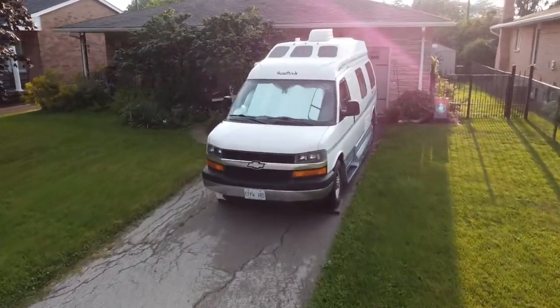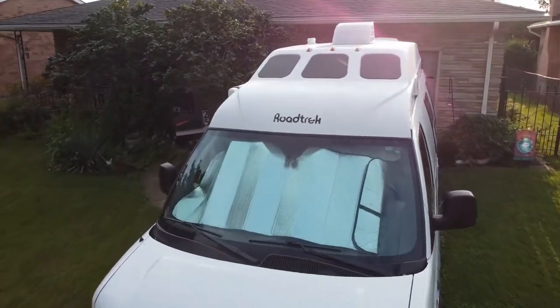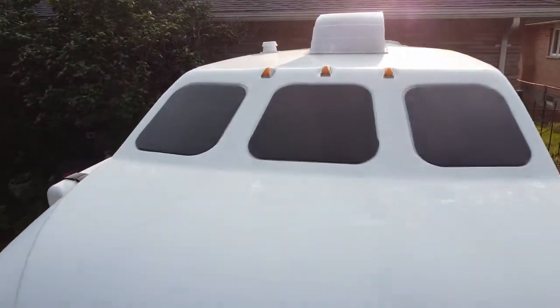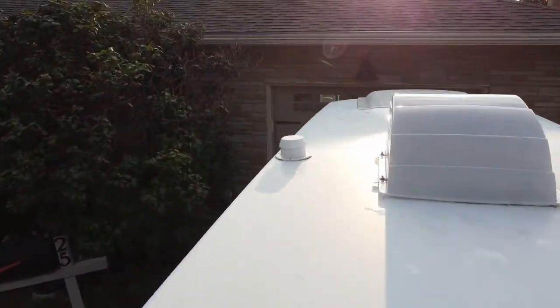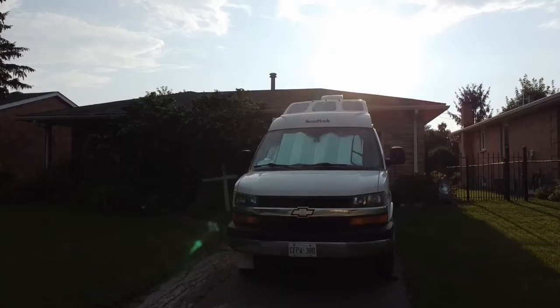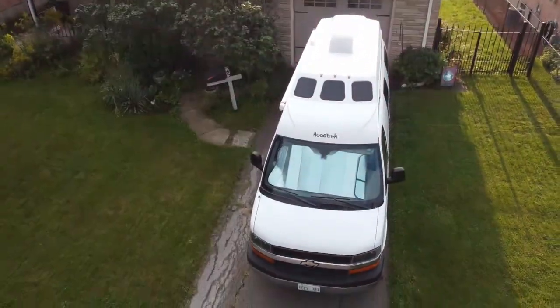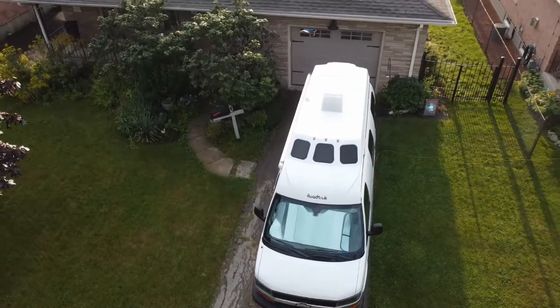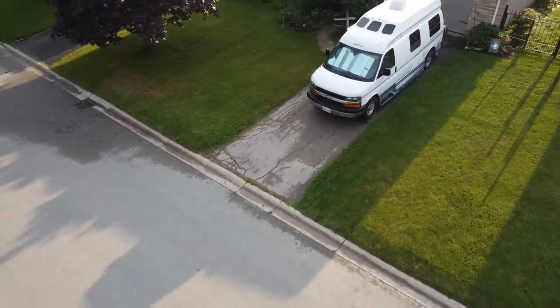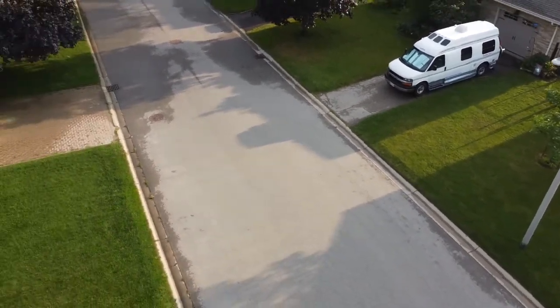What have we learned? At the front end of things, with the fan running the fridge does seem to cool down a little faster. But after four hours, fan or no fan, the fridge is at about the same temperature. It does draw it down quicker, so one way or the other - if your fridge is in good shape - it's going to get cold to industry standards in about six hours or so. Thanks for watching, have a great day.